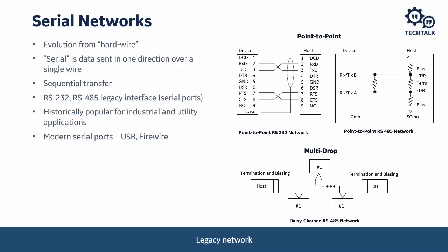The physical media traditionally used for serial communication — which we're all aware of — is the RS-232 or RS-485 interface. The RS-485 has the advantage of being able to interface with many devices within certain limitations, whereas RS-232 is usually a point-to-point device-to-device communication. Advantages of using serial include: we have a good understanding of it, it's been around a while, it's widely available, we know how to configure it, it's very efficient, and it supports DNP and Modbus, which have been popular protocols within the industrial and utility market.